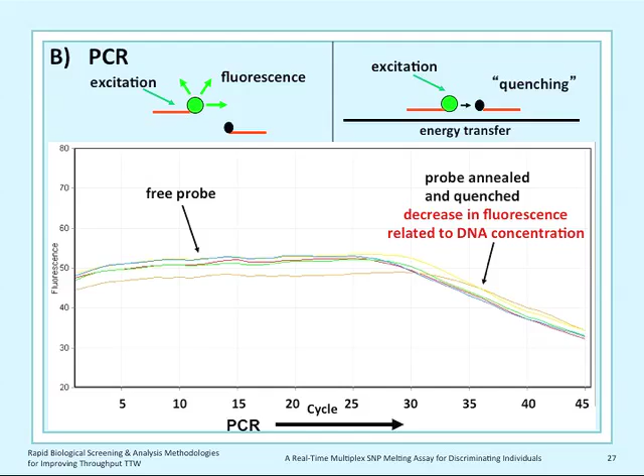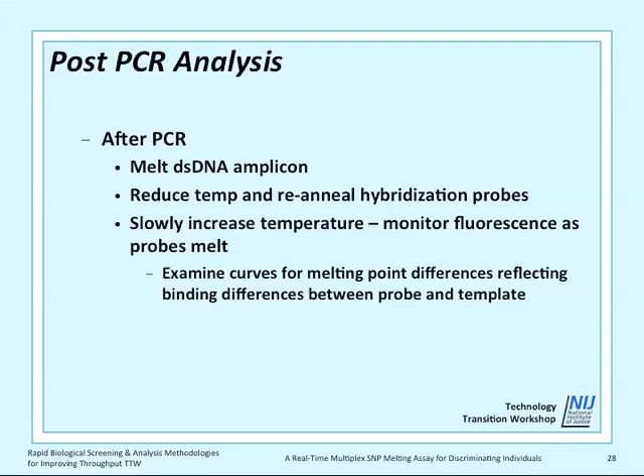After PCR, the double-stranded amplicon is melted, the temperature is reduced, and the hybridization probes are re-annealed. The temperature is slowly increased, and the fluorescence is monitored to note the temperature at which the probe melts from the template. The melt analysis software allows the examiner to quickly review the differences in melting points, which reflects the binding differences between the probe and the template. At temperatures below the Tm for the sensor probe, the probe binds to both matching and mismatching sequences. The anchor probe binds adjacent to the sensor probe, quenching the fluorescence from the sensor probe.